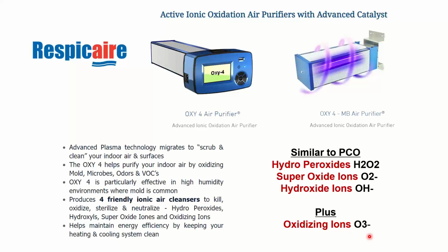Great. Some people don't want ozone in their space, right? Every entity has its own limit on how much ozone you can have in a space. The most restrictive, the most conservative is FDA, and they will allow up to 0.05 parts per million of ozone in a space before they say, okay, you have too much ozone. Most of these devices will produce between 0.02 and 0.04. Now, they can produce more or less. It depends on the size of the device you bought versus the size of the space you have and how much the space is ventilated. But if they're sized correctly, we'll be hovering around 0.02, 0.03, 0.04 parts per million, which is well below the FDA limit and certainly under the limit of other entities.